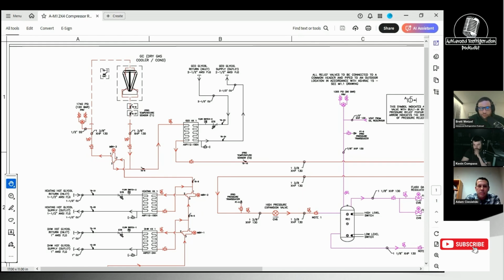With that being said, fan control is really critical, and our aim is to keep the response time nice and slow. And it's almost better to maybe vary off a set point a little bit and just keep fan speed more constant. If your set point is 60 and you're floating up and down lazily between 58 and 63, who cares really? But if the fan is now chasing that 1 or 2 degrees really tight, then you can lose control. My point being is systems have very slow fan control.